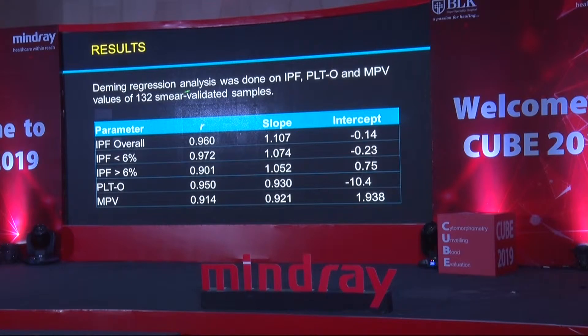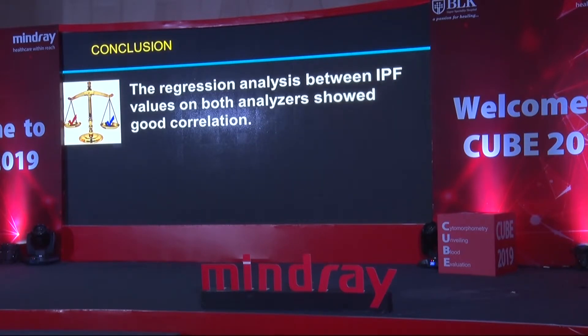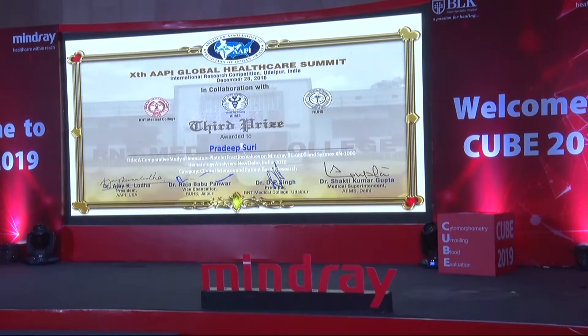We performed Deming regression analysis, and the R value was robust — more than 0.9 across IPF less than 6, IPF more than 6, optical platelet, and mean platelet volume. However, IPF in patients with IPF more than 6% showed slightly lower correlation than the general IPF group with less than 6%, which was expected because IPF more than 6% is usually seen in thrombocytopenic patients likely to have slightly higher analyzer CV for platelets. The conclusion was that regression analysis between IPF on both analyzers showed good correlation. We presented this paper at the AAPI Global Healthcare Summit in Udaipur and received a third prize.